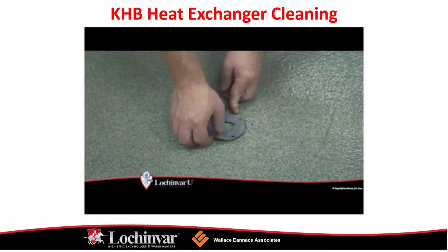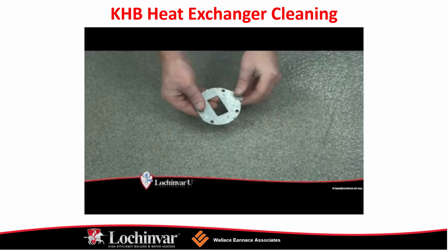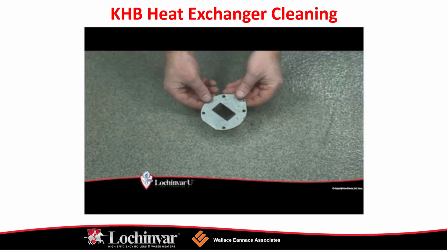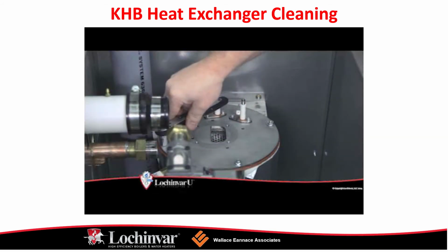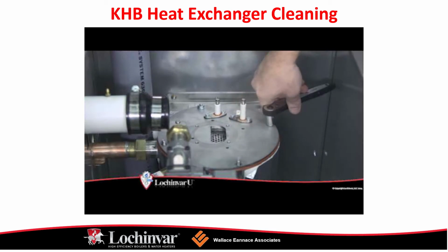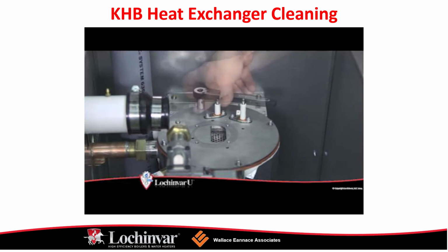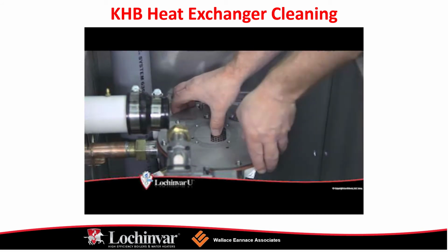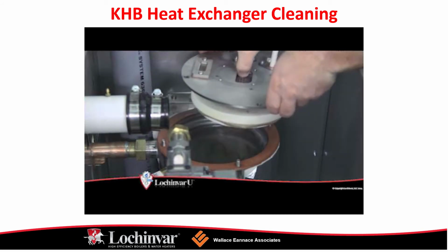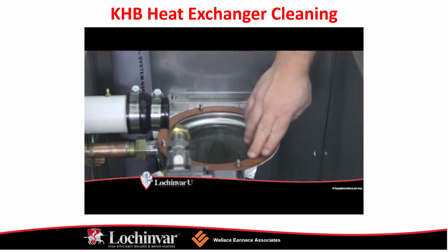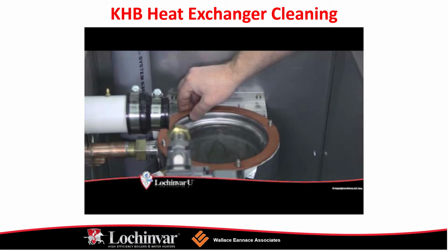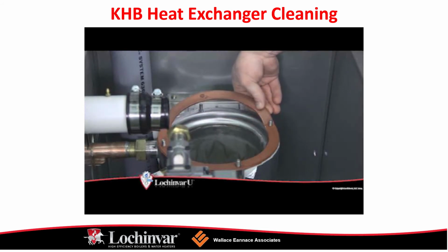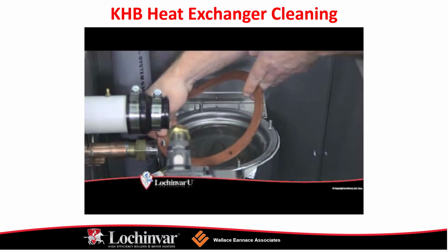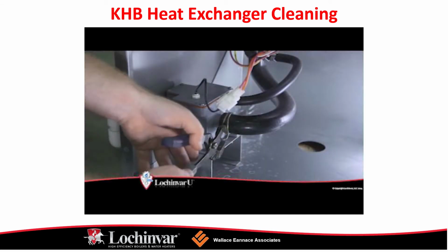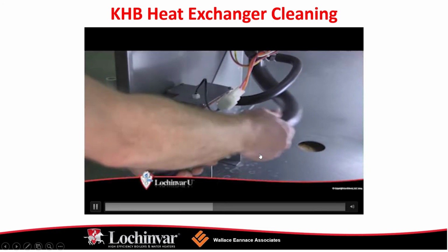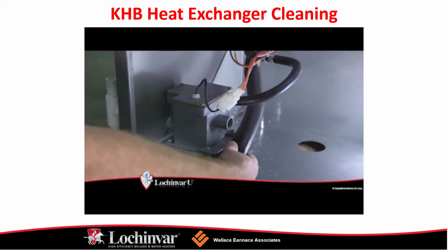Using a Phillips head screwdriver, remove the 4 screws securing the bezel to the unit and remove the bezel from the front of the unit. Then locate and disconnect the 2 wiring harness connections on the combustion blower. Now remove the wiring from the flame rod, spark igniter, and ground terminals from the heat exchanger door. Next, remove the rubber hose from the air intake pipe and loosen the band clamp securing the air inlet to the Venturi. Now, loosen the union on the Venturi. You should now remove the 4 Allen head screws securing the combustion blower to the unit.